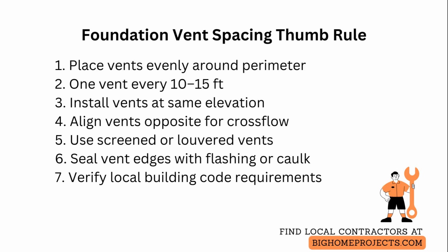If your climate is humid or you see moisture signs such as condensation or mold, consider crawlspace encapsulation with a vapor barrier and controlled ventilation or mechanical ventilation instead of relying solely on passive vents. Always verify local building code for minimum net free vent area and any specific spacing rules before finalizing placement.